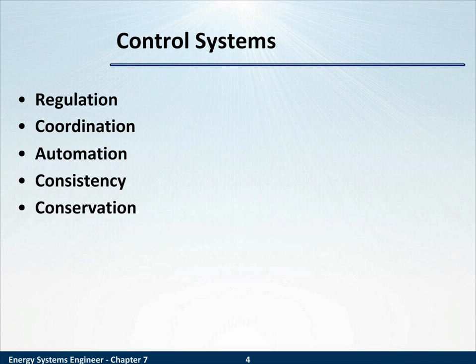An example is, let's say you have 200 offices in an office building. Your control system can monitor outside air temperature and humidity and predict what it will be in the next 6 hours. It can measure indoor temperature and humidity in your 200 office spaces. And it can make the decision whether to be in chilled water mode or economizer mode, a decision you could never make because you couldn't get the data and make the decision fast enough. But the control system can conserve energy by enabling that decision that's otherwise out of reach.